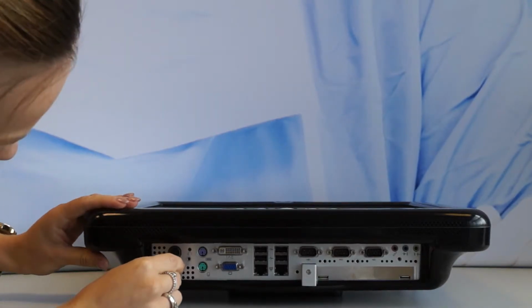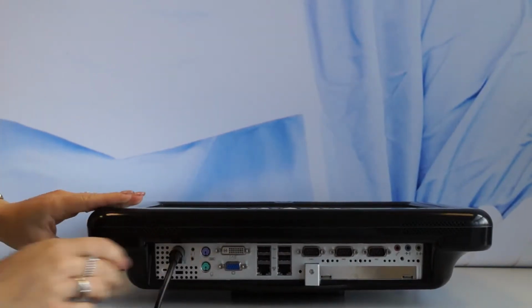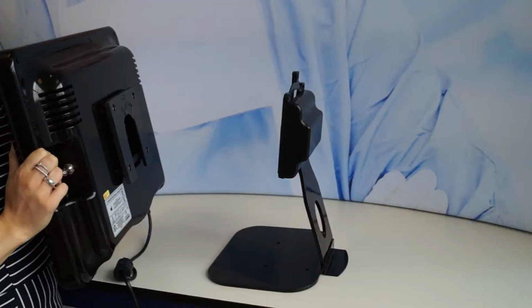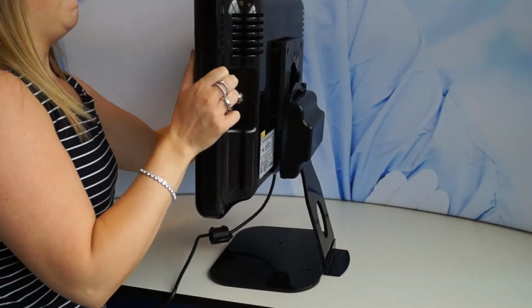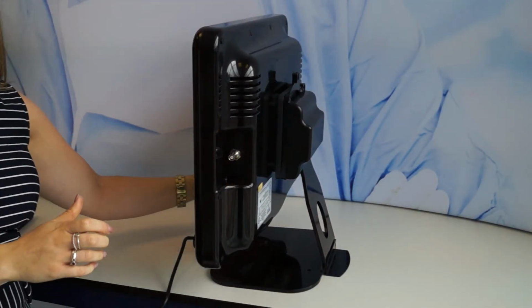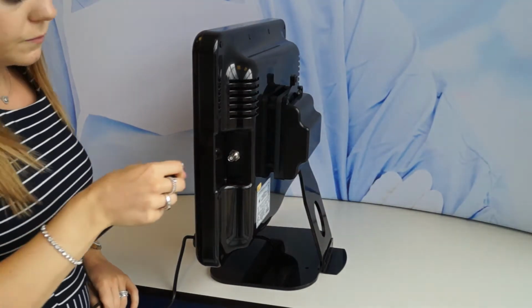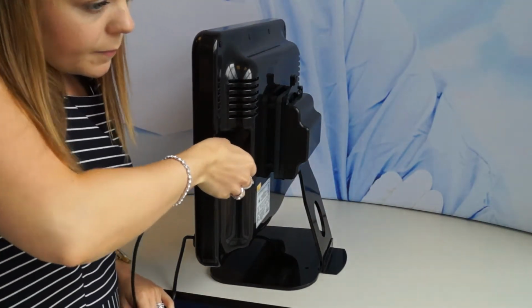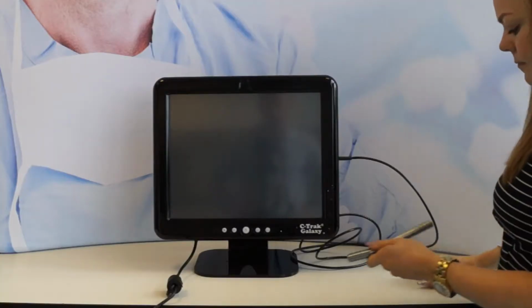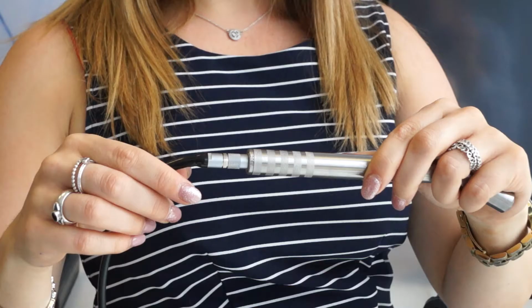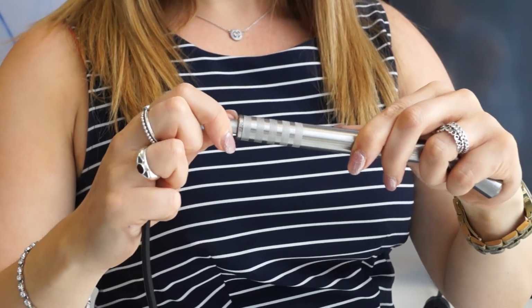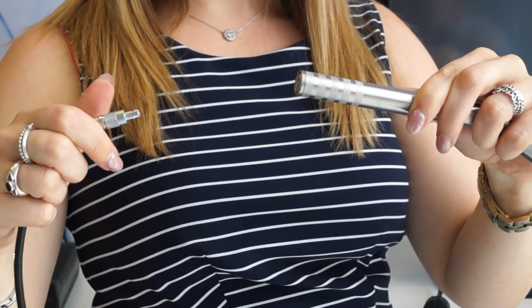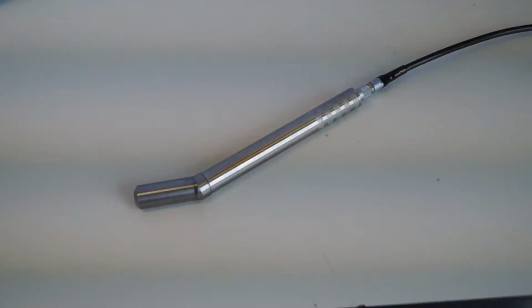When setting up the Galaxy, it is easier to insert the power cable to the screen when it is lying flat prior to sliding it onto the quick release bracket. Connect the probe cable to the right hand side of the screen and the other end to the bottom of the probe. To release the probe cable from the end of the probe, gently pull the release sleeve backwards to detach. Inside the probe contains a crystal and glass tube, so they are very fragile. If it is dropped or mishandled, it can break.